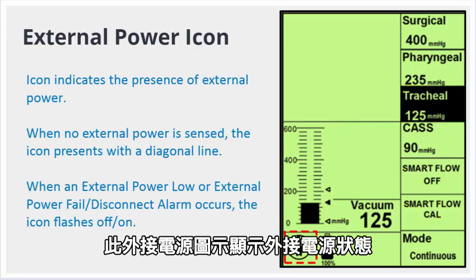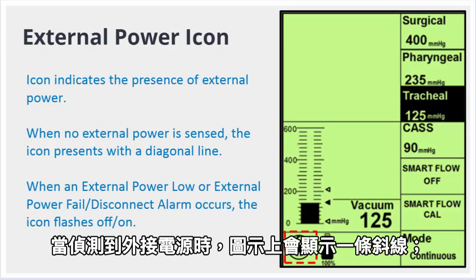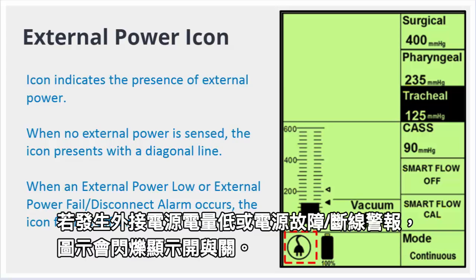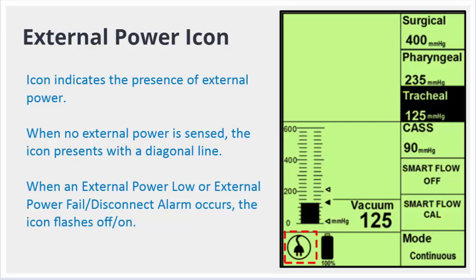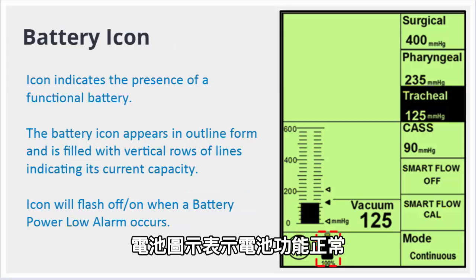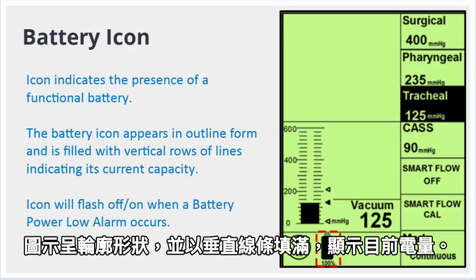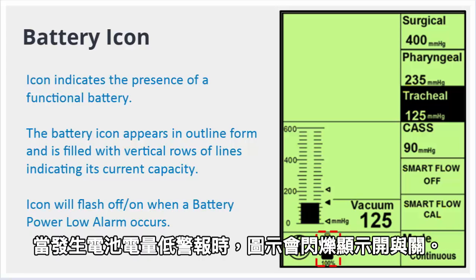This external power icon indicates the presence of external power. When no external power is sensed, a diagonal line will display over the icon. When an external power low or external power fail disconnect alarm occurs, the icon flashes off-on. The battery icon indicates the presence of a functional battery. The battery icon appears in outline form and is filled with vertical rows of lines indicating its current capacity. The icon will flash off-on when a battery power low alarm occurs.